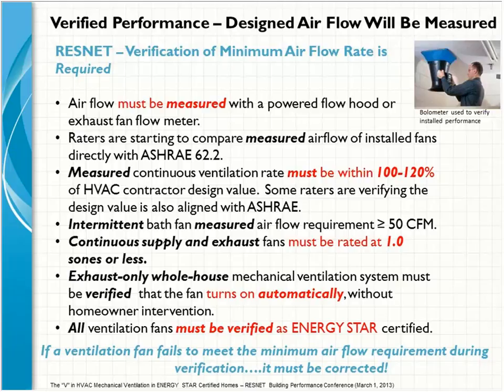And with the ASHRAE 62.2 code, it also has to function automatically. We can't rely on a multifamily occupant or even a single home occupant, homeowner, to run the equipment. It has to be automatic. So we would have it programmed to run either intermittently X number of minutes per hour or continuously to meet the number of CFM that we need exchanged from that building on an hourly basis. And the equipment must be ENERGY STAR rated.